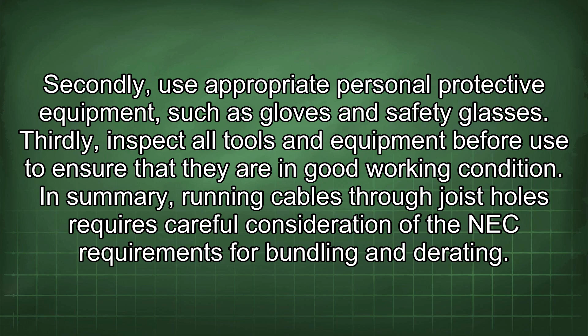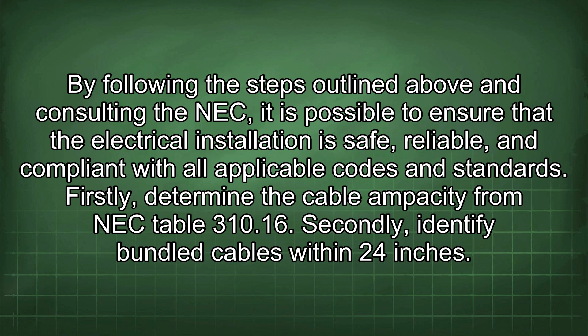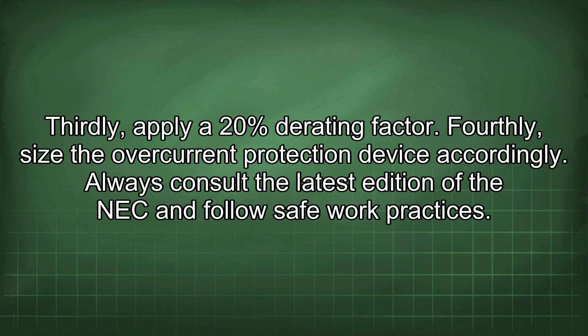Firstly, determine the cable ampacity from NEC Table 310.16. Secondly, identify bundled cables within 24 inches. Thirdly, apply a 20% derating factor. Fourthly, size the overcurrent protection device accordingly. Always consult the latest edition of the NEC and follow safe work practices.